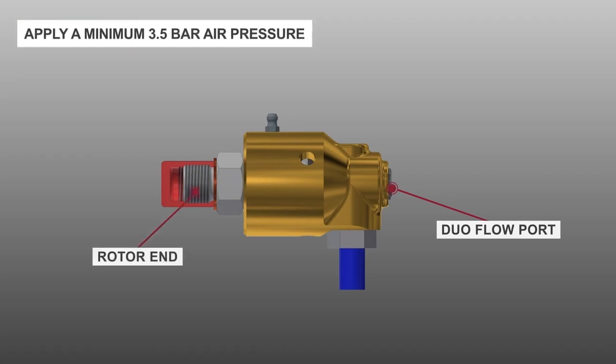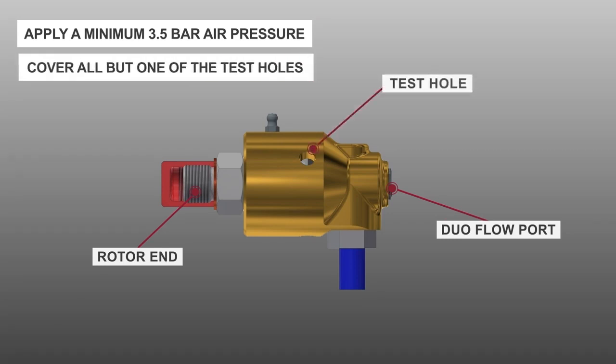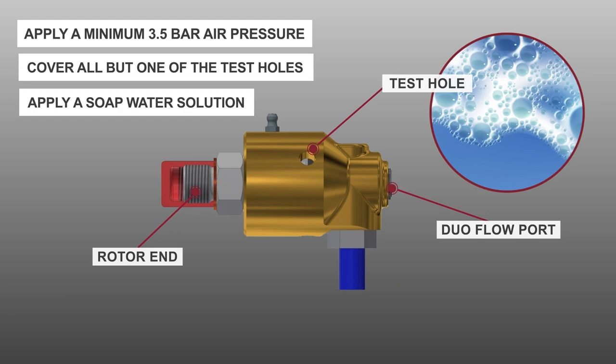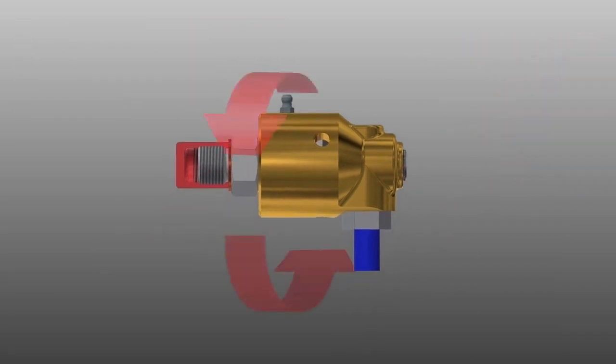Apply a minimum 3.5 bar air pressure. Cover all but one of the test holes and apply a soap water solution or bubble soap over the open test hole. Rotate the union by hand. If no soap bubble rises, the union passes the test.